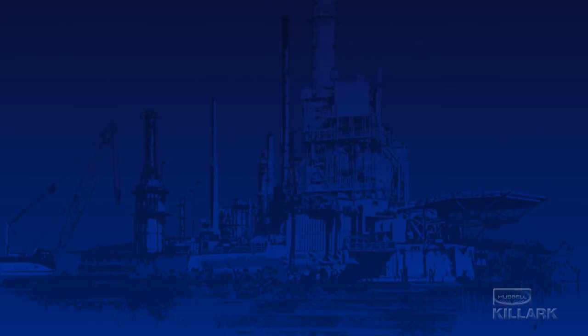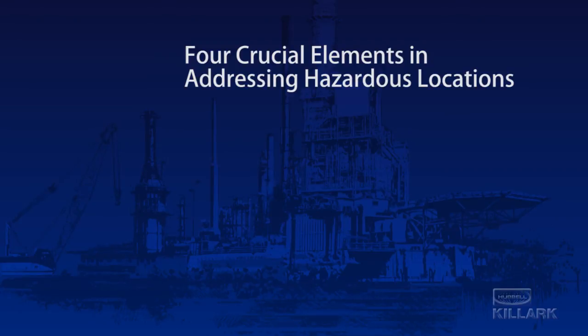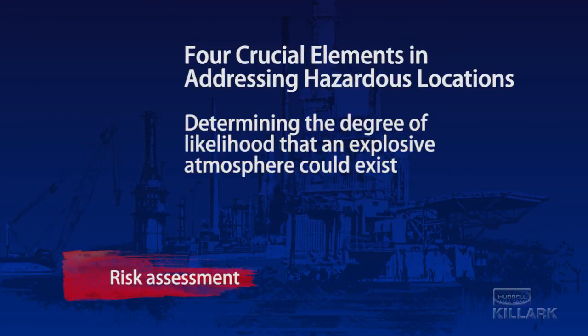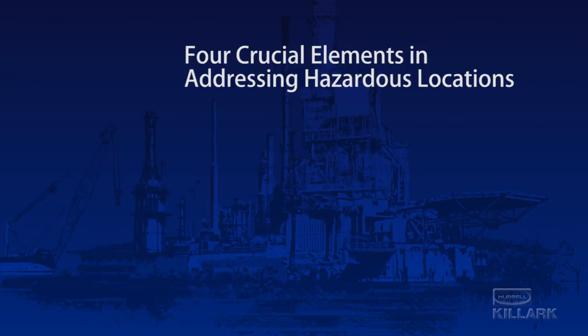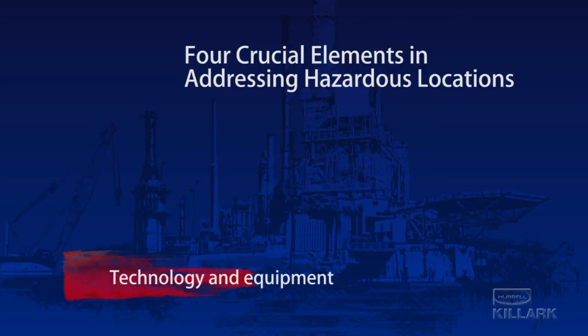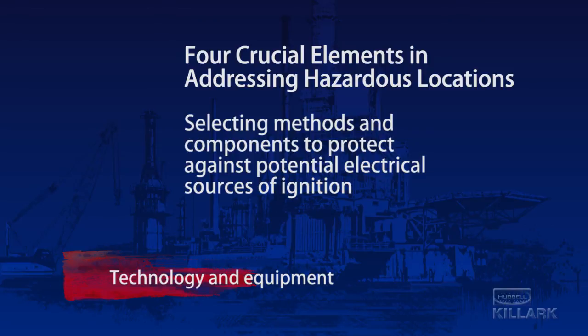Four crucial elements guide the overall process for addressing the use of electrical equipment in hazardous locations, regardless of the system used. The first, and most fundamental, is conducting a risk assessment. This is an evaluation of the degree of likelihood that an explosive condition could develop in a process area or other location because of flammable material in the atmosphere. The second consideration involves selecting the type of technology and specific equipment to protect against the potential for electrical components becoming a source of ignition. Installation practices will also help guide the selection once the risk assessment has been completed.